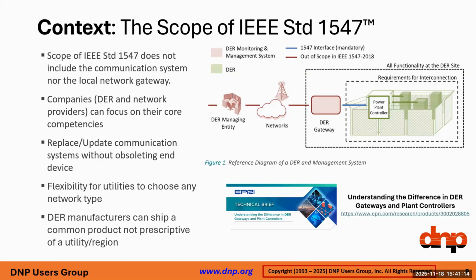It covers how DERs behave when voltage or frequency are outside of bounds, defines grid supportive capabilities DERs must support, and otherwise sets a default for DER behavior on the grid. A key aspect is that in 2018, communication capabilities were added to allow area EPS operators or others to update set points for grid supportive capabilities as local grids changed over time, requiring 2030.5, SunSpec Modbus, or DNP at a local DER communication interface.